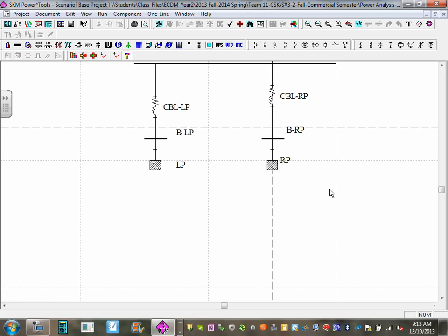Now we're doing it this way this time, guys. Next project, we're going to be using something called schedules. I don't want you to build a schedule in this. The way Adam and Mishad do it, if you see them, they do it differently. They have schedules. They add a schedule. We will do that one next time. This is the easier way of doing it. Since you guys have never been introduced to this, you lump some of the load as one big chunk of load for the analysis. So we have 33 kVA of receptacle load and 69 kVA of lighting load. Can I have thumbs up, Chad? We fully understand that one?